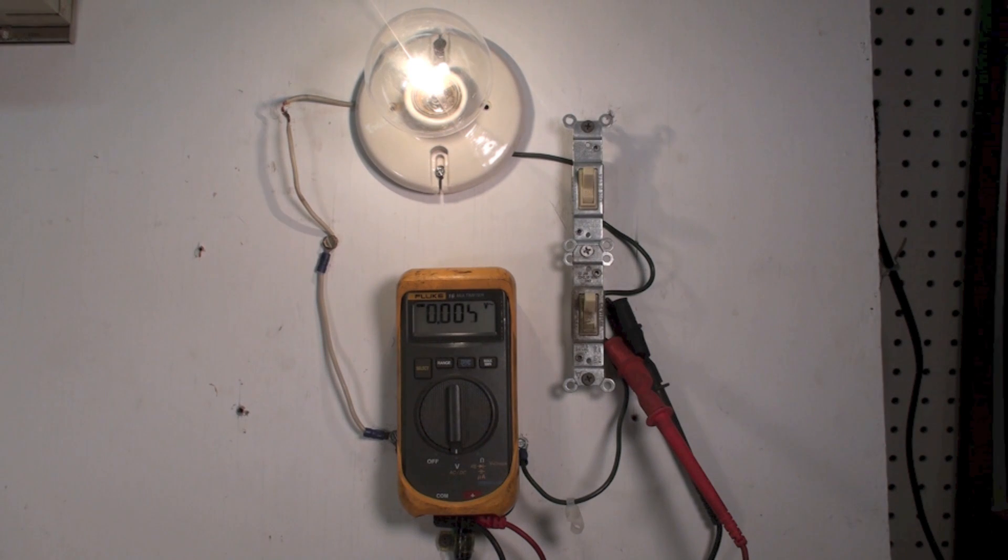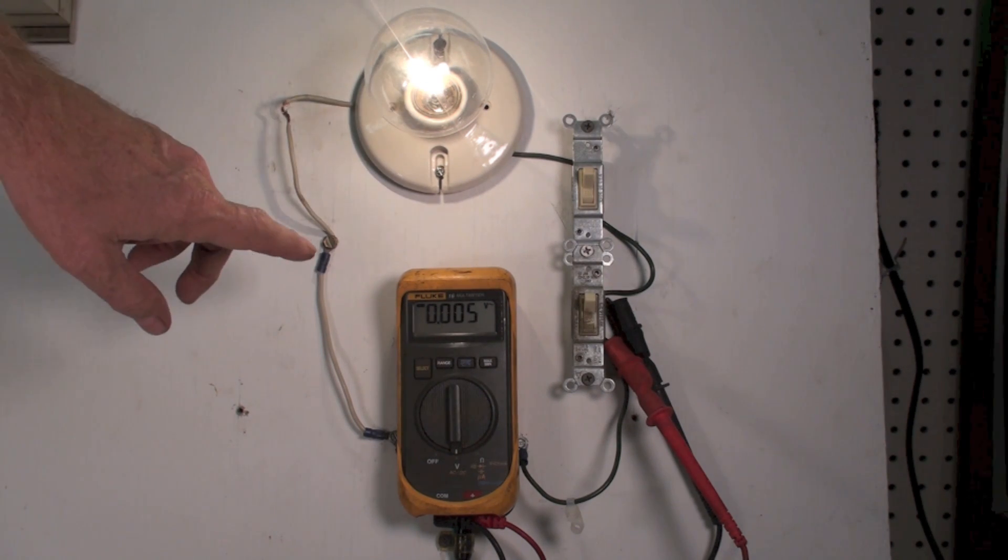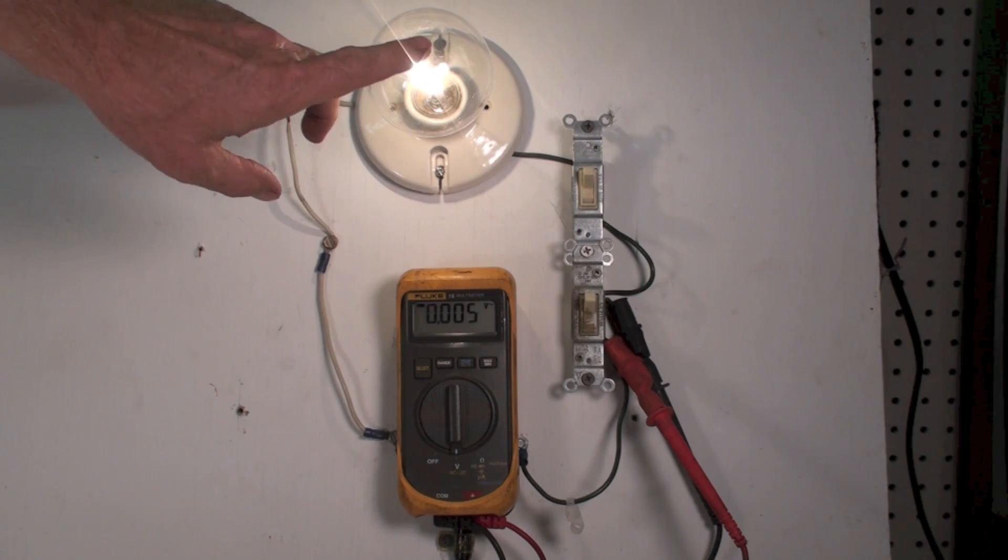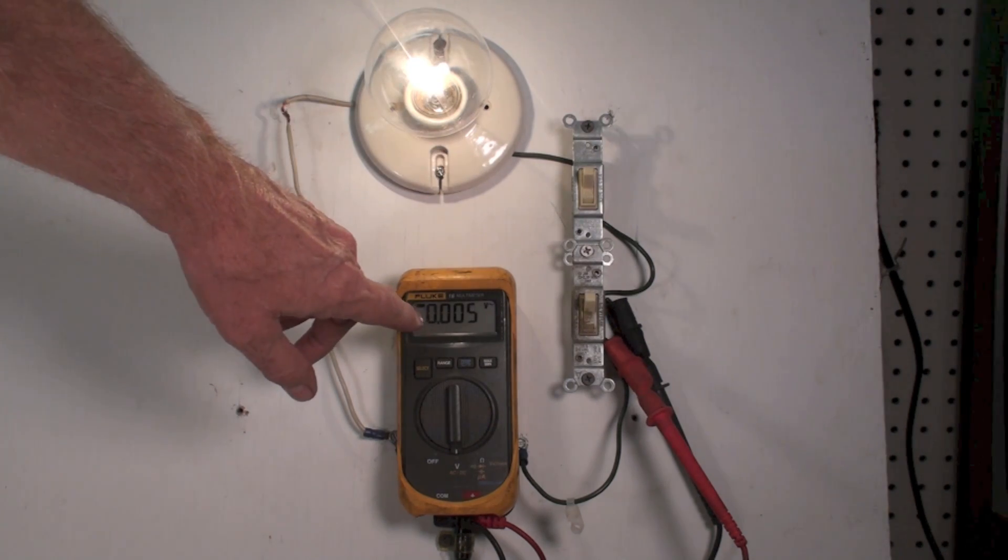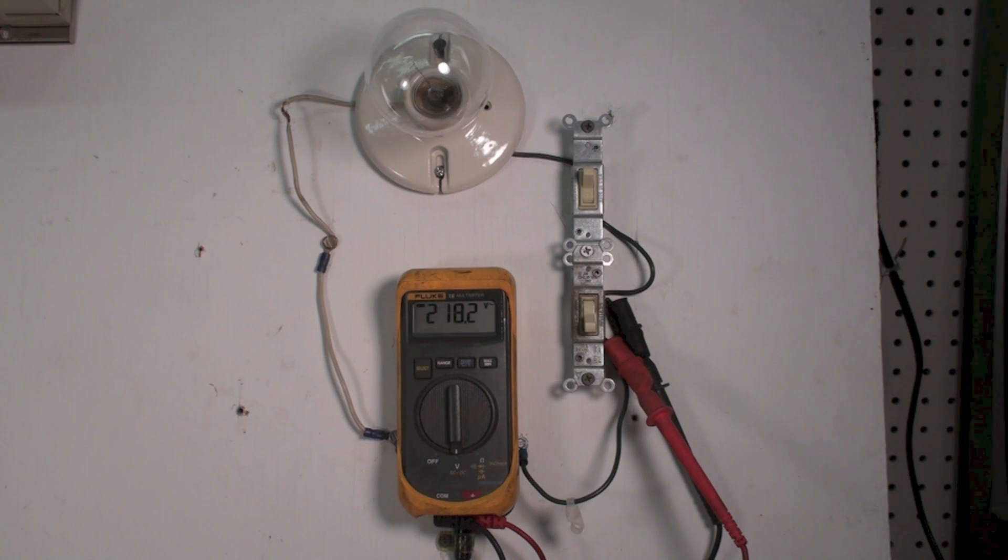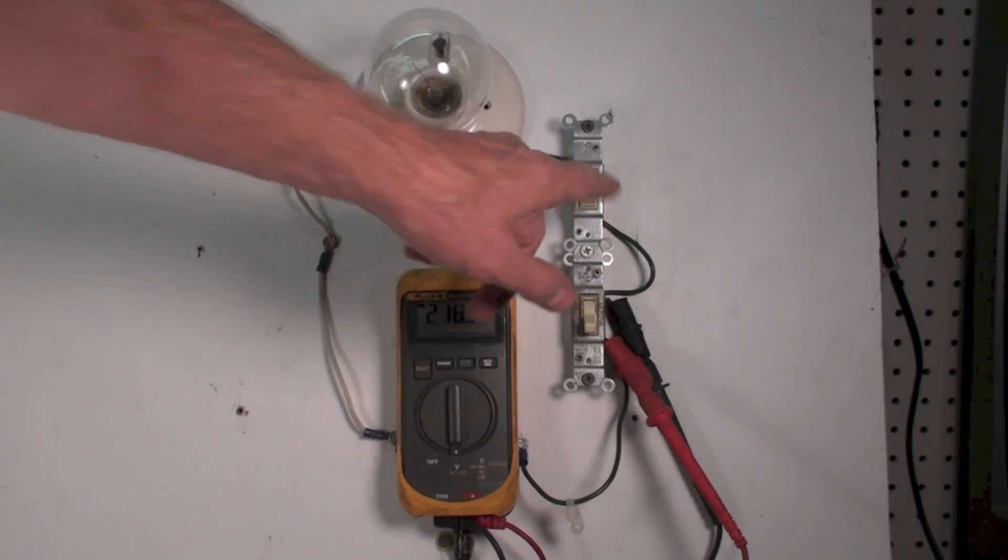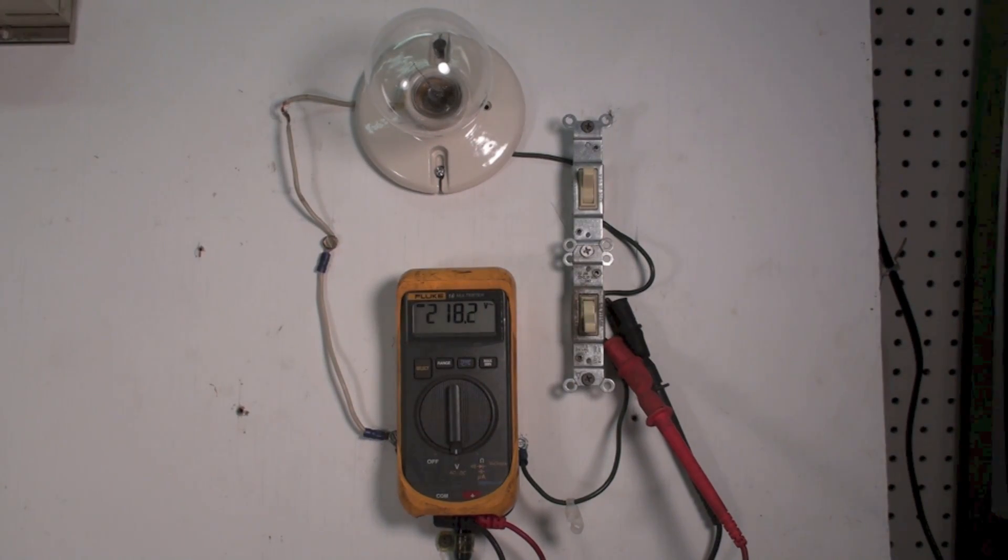Both of these switches have to be on for this thing to work. So I turn this one on and now I'm working. The load is working, I'm still reading zero. The only way I can read the line voltage is to shut this switch off and leave this switch on, and the load is still good.